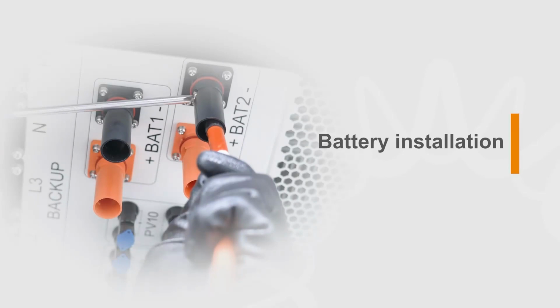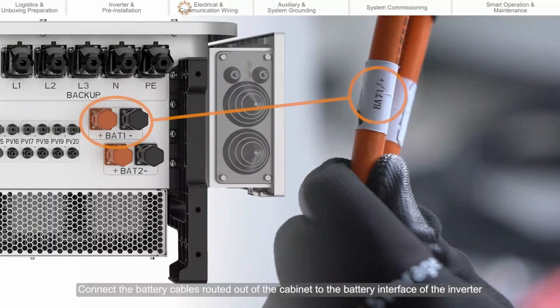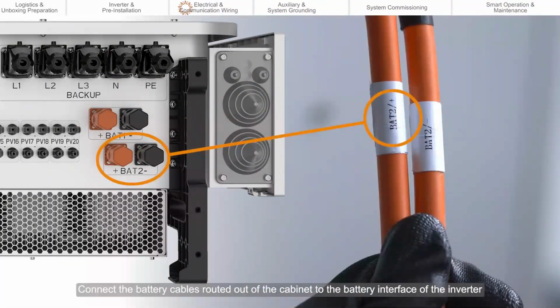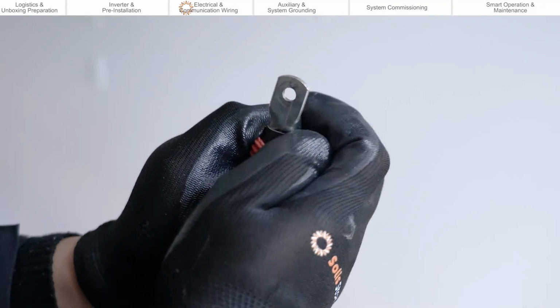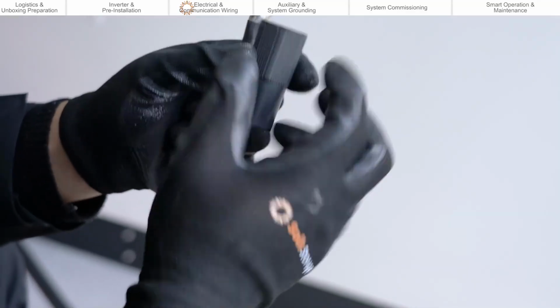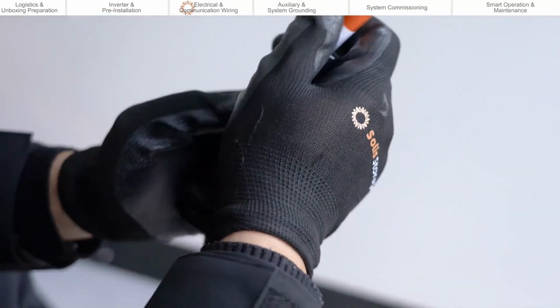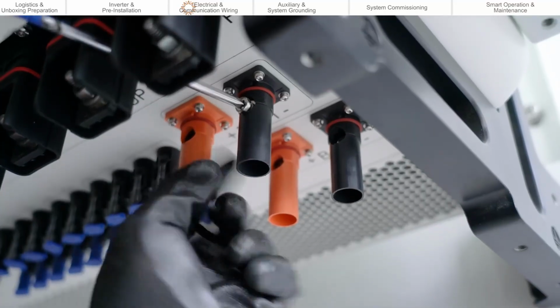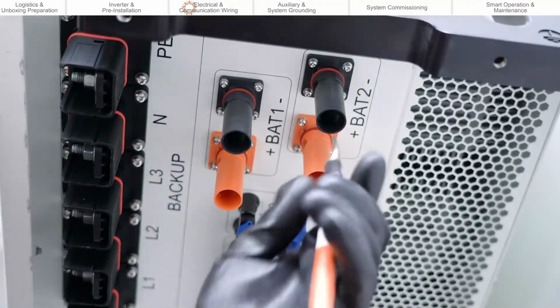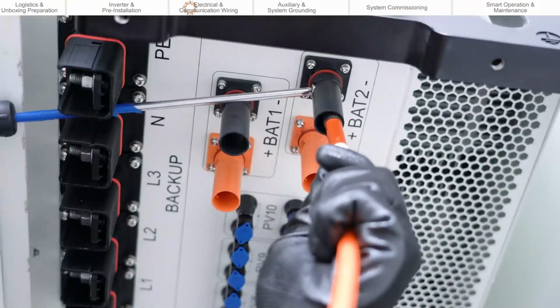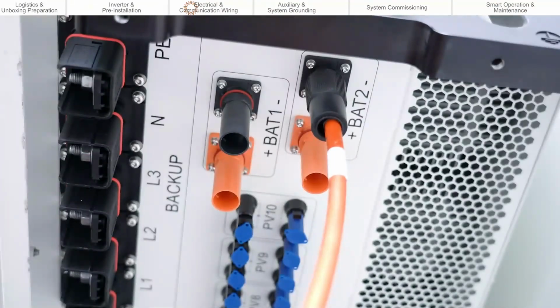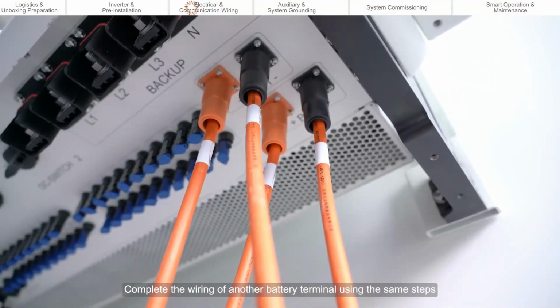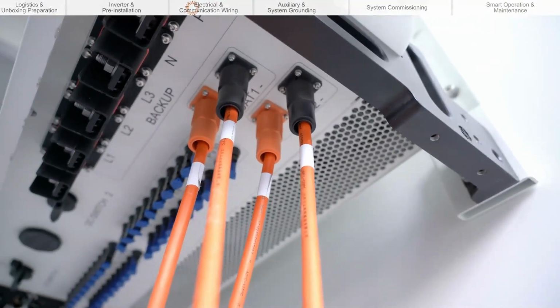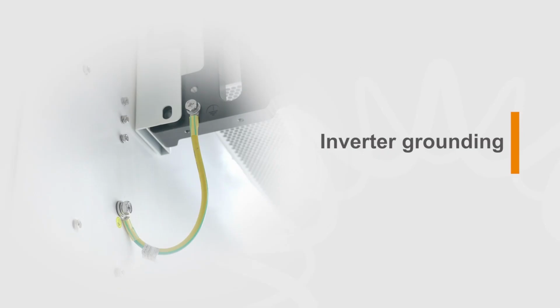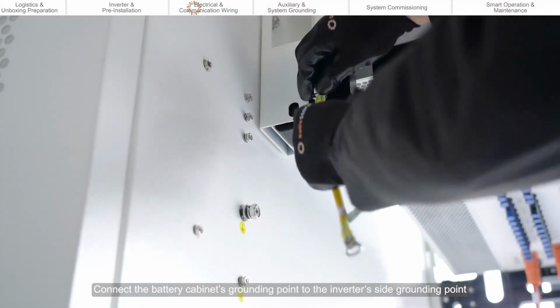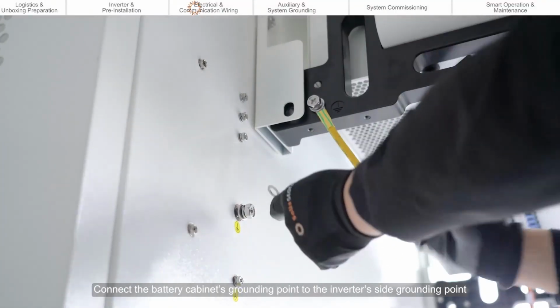Battery installation. Connect the battery cables routed out of the cabinet to the battery interface of the inverter. Complete the wiring of another battery terminal using the same steps. Inverter grounding. Connect the battery cabinet's grounding point to the inverter's side grounding point.